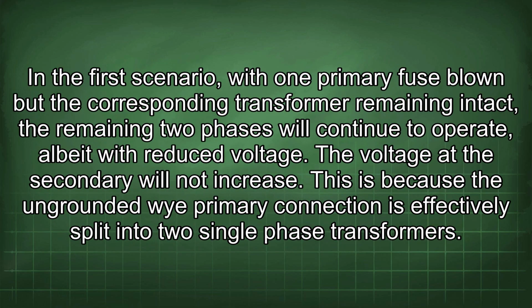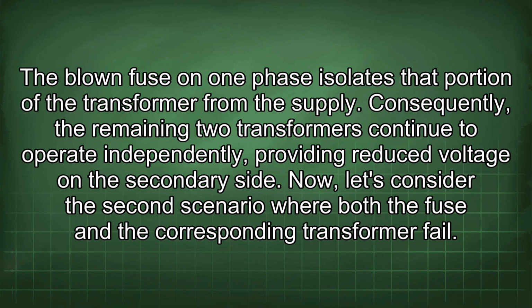In the first scenario, with one primary fuse blown but the corresponding transformer remaining intact, the remaining two phases will continue to operate, albeit with reduced voltage. The voltage at the secondary will not increase. This is because the ungrounded Wye primary connection is effectively split into two single-phase transformers. The blown fuse on one phase isolates that portion of the transformer from the supply. Consequently, the remaining two transformers continue to operate independently, providing reduced voltage on the secondary side.